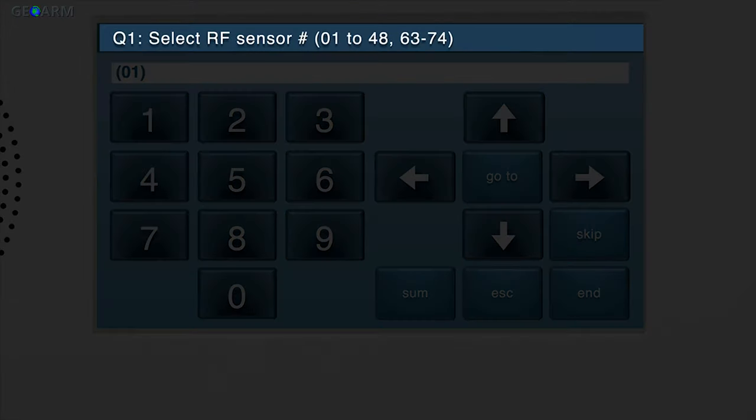You'll see Q1 Select RF Sensor Number displayed in the upper ribbon of the screen. System Configuration is navigated via Questions and Sub-Questions. Wireless zones are programmed in Q1, so we are already on the correct question for wireless devices.